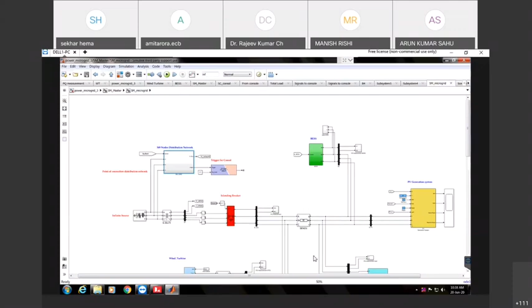This is the distribution network as of now. If you see these two distribution networks, this is the main grid I am considering, and you can see this islanding breaker here. If a fault is happening at any of the buses in the distribution network, this breaker will be opened immediately, so that this microgrid will be islanded and given to a local power system.